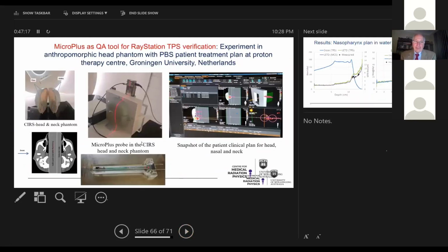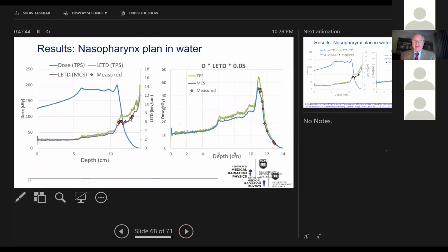We did, for example, a beautiful experiment in a phantom. You can see an anthropomorphic phantom. We did planning with the microdosimeter and delivered a pencil scanning beam. You can see our microdosimeter, a very portable probe. We can measure the LETD distribution and compare it with the RayStation treatment planning system, which predicts this LETD, and we get very nice agreement. We can see this in particular for a nasopharynx plan in water. And finally, we can see the additional dose which should be delivered to the patient. Again, it's a beautiful agreement with the treatment planning system.